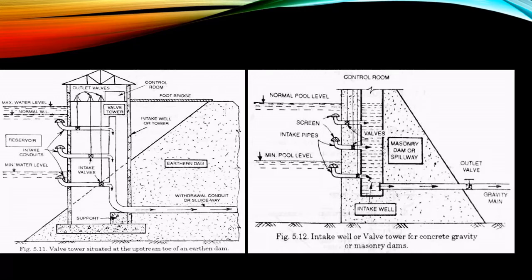You need to provide multiple penstocks. Penstocks means pipelines to take water inside, or openings. You need to provide more than two or three or four penstocks or openings into reservoirs. Reservoir intake has more openings than river intake because the water depth in reservoir is greater than river. That's why you need to provide more openings or pipelines or penstocks at different depths to consider, so that you can draw water throughout the year.